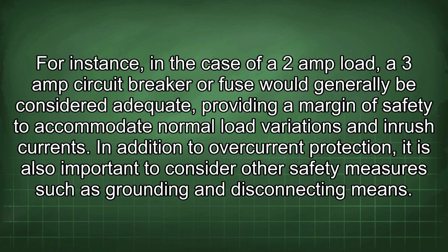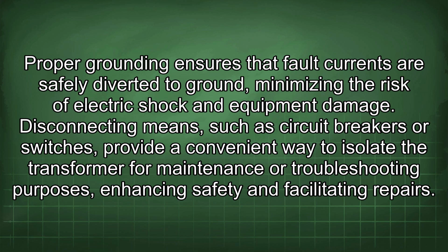In addition to overcurrent protection, it is also important to consider other safety measures such as grounding and disconnecting means. Proper grounding ensures that fault currents are safely diverted to ground, minimizing the risk of electric shock and equipment damage. Disconnecting means such as circuit breakers or switches provide a convenient way to isolate the transformer for maintenance or troubleshooting purposes, enhancing safety and facilitating repairs.